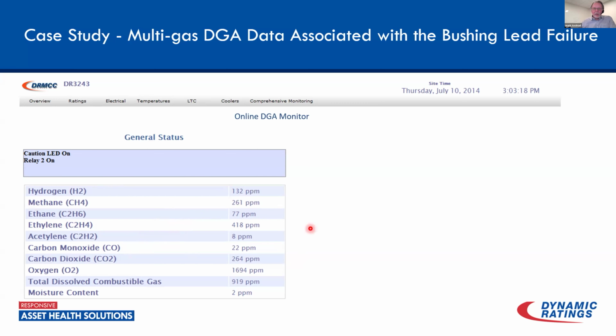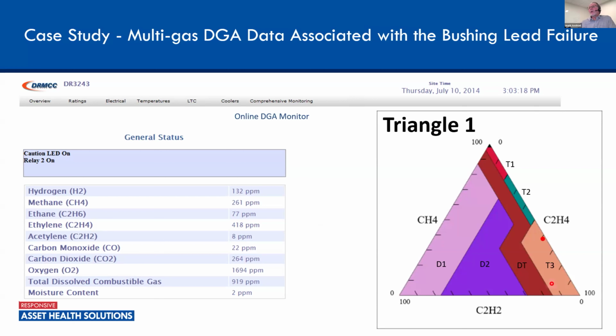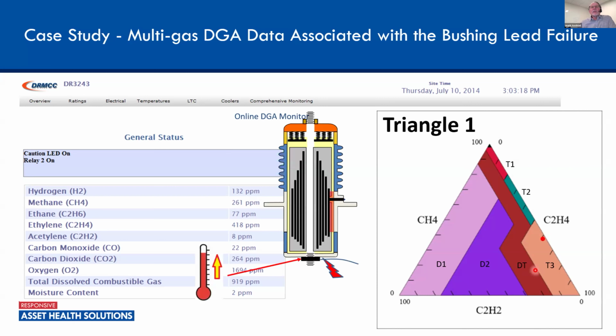So if we do an analysis on that, looking at it in the Duval triangle, here we had a T3 thermal fault, which is a fairly high temperature thermal fault on that transformer. And that's what was driving it. Again, not a lot of hydrogen, so it didn't really identify partial discharge as a problem. The level of methane definitely indicated to me that there was some partial discharge there as well. But from the overall diagnostic using the Duval triangle, it said it was more of a T3 thermal fault. And in this situation, it was due to a loose bottom terminal connection on that bushing that was driving that. So, a good example of how you can utilize both the partial discharge monitoring and the DGA monitor in conjunction with one another to identify what's going on.